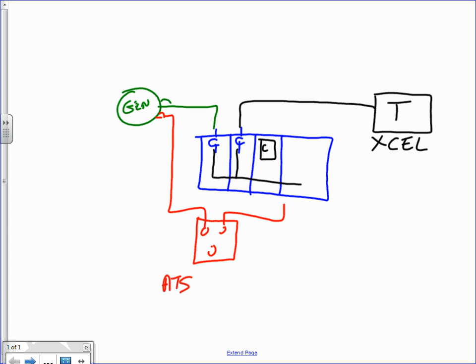Now, one thing that I'll mention on this front is, there's typically an output breaker on the genset as part of the genset, but I mentioned that we're going to deal with our life safety loads. So I'm going to have an ATS. So we do that with an additional breaker off of the genset that feeds my life safety loads. And then in this case, maybe I come up here for my utility, and then this goes to my life safety panels for egress and exit lights.